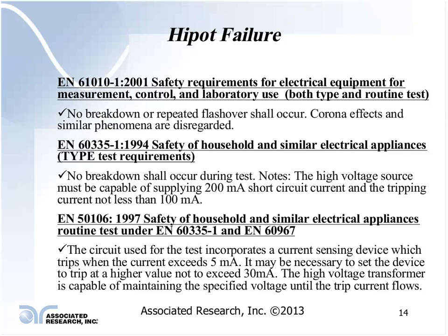If the operator makes a mistake and they come across this high voltage potential, is it going to create a startle reaction where they just receive a slight electrical shock, or is it going to be lethal, where it could either do some serious damage or potentially kill an operator? And whenever you're talking about an instrument with this kind of current capacity, it has the capability of doing that.